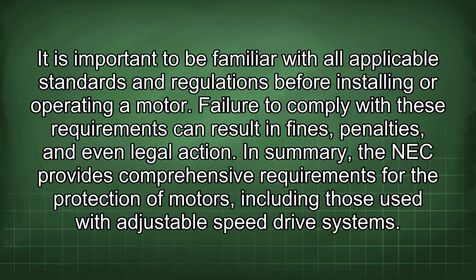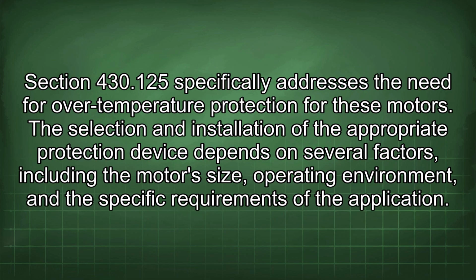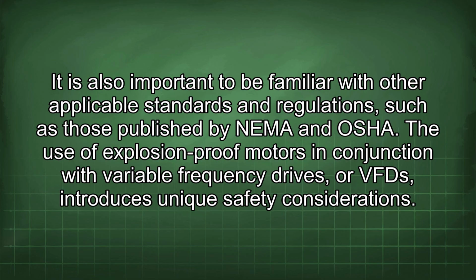In summary, the NEC provides comprehensive requirements for the protection of motors, including those used with adjustable speed drive systems. Section 430.125 specifically addresses the need for over-temperature protection for these motors. The selection and installation of the appropriate protection device depends on several factors, including the motor size, operating environment, and the specific requirements of the application. It is also important to be familiar with other applicable standards and regulations, such as those published by NEMA and OSHA.